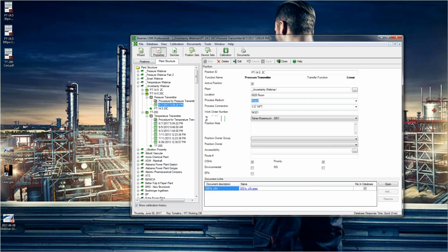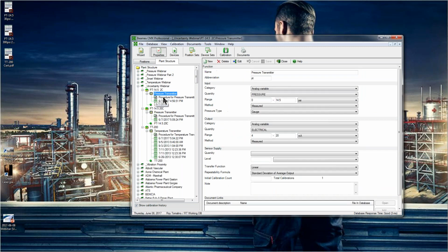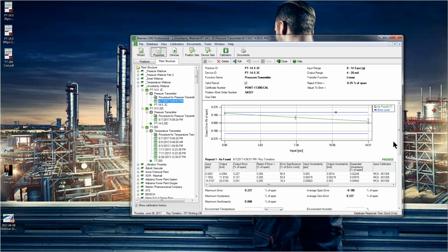Now, let me click on the 30 PSI module. And you can see that those guard bands are much smaller, much tighter. Here, if the guard bands are a quarter of the size of our full tolerance, then we're having a 4-to-1 test uncertainty ratio. And I'm just guessing visually, we might even be closer to 5-to-1 on this one. And it is possible to even use a 15 PSI module to get the test uncertainty ratio even larger.